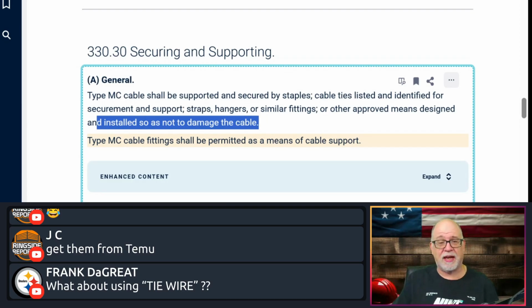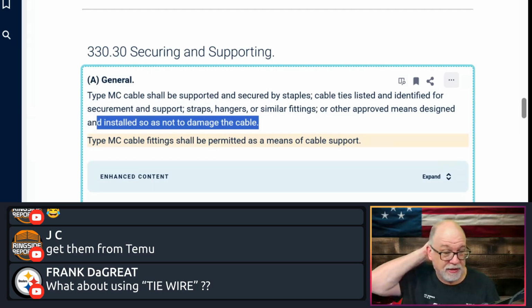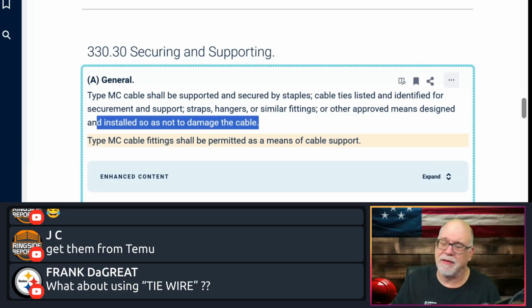In fact, as an AHJ or a deputy for the AHJ, I approved many securements supported with MC cable above suspended ceilings with the use of tie wires, right? And I had no problem with it at all. Now, the only problem I may have with it is if you're using something that would be a dissimilar metal and you're tying it. But in general, tie wires are fine. It's certainly not going to damage it. So I would think an AHJ would have no problem with that at all. But again, always check with your AHJ just to make sure.